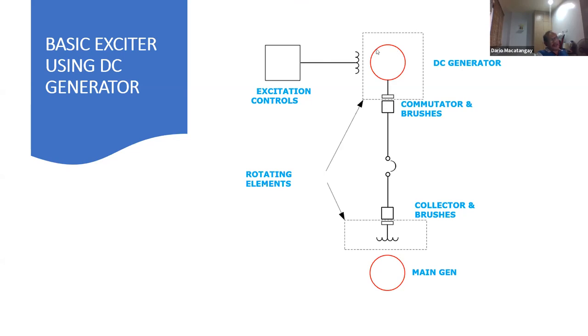So to complete the system, you need a source of that excitation. So you need a DC generator. The DC generator has a commutator and brushes instead of slip rings and brushes. And you need to run this generator. You can see that this portion is rotating as well as this one. They are on one common shaft, so the DC generator and this exciter are both rotating, revolving. DC is provided here, collected here at the brushes. This portion here is stationary. Then it is transferred back to the revolving field through collector rings and brushes.